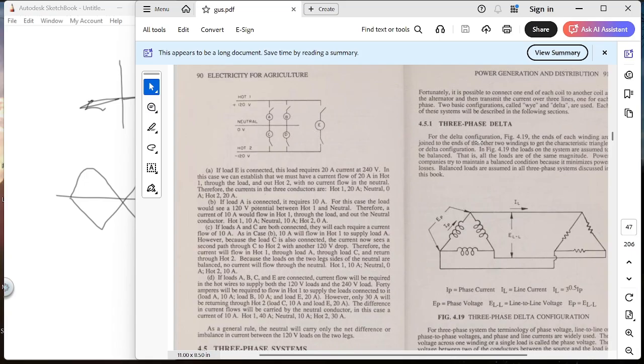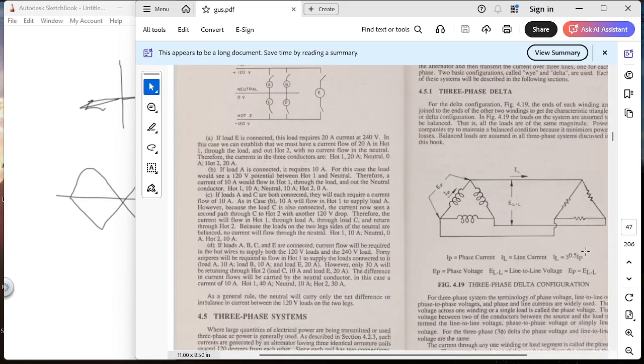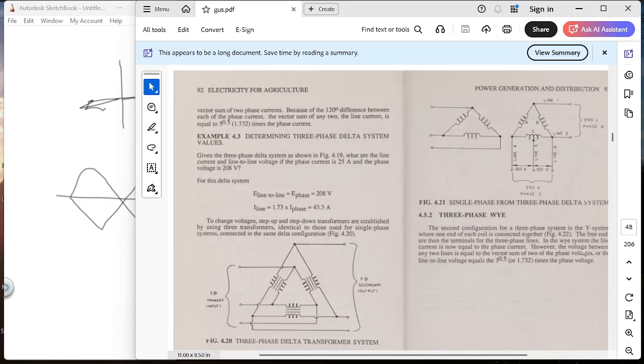This would be the three phase: delta to delta. You can also have delta to Y, as we talked about before. And off the three phase you can take, say, your 240 or 480, and then the secondary would be three phase to single phase by doing this. That's one of the ways of doing it.